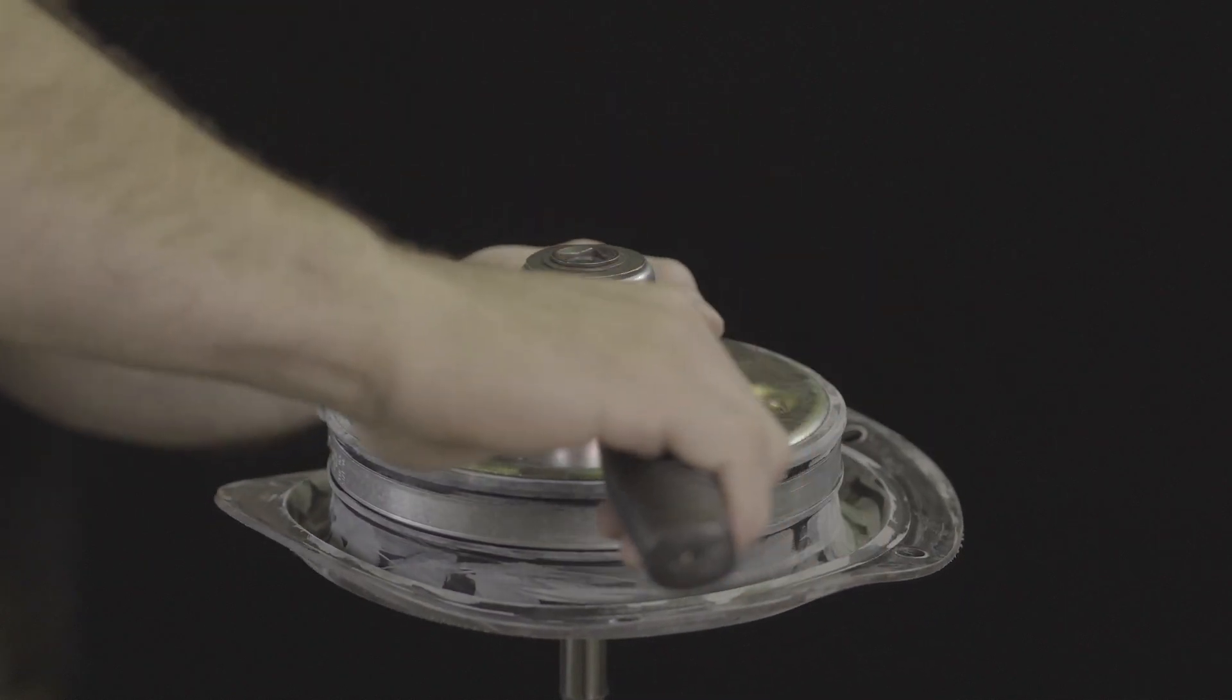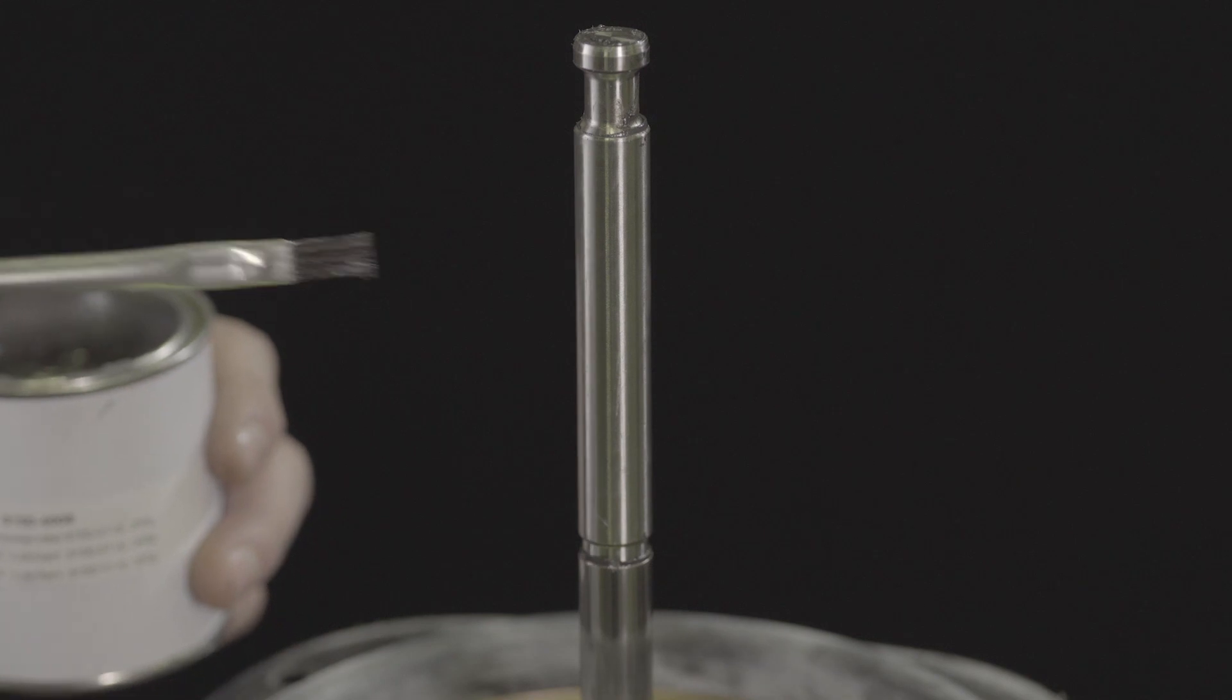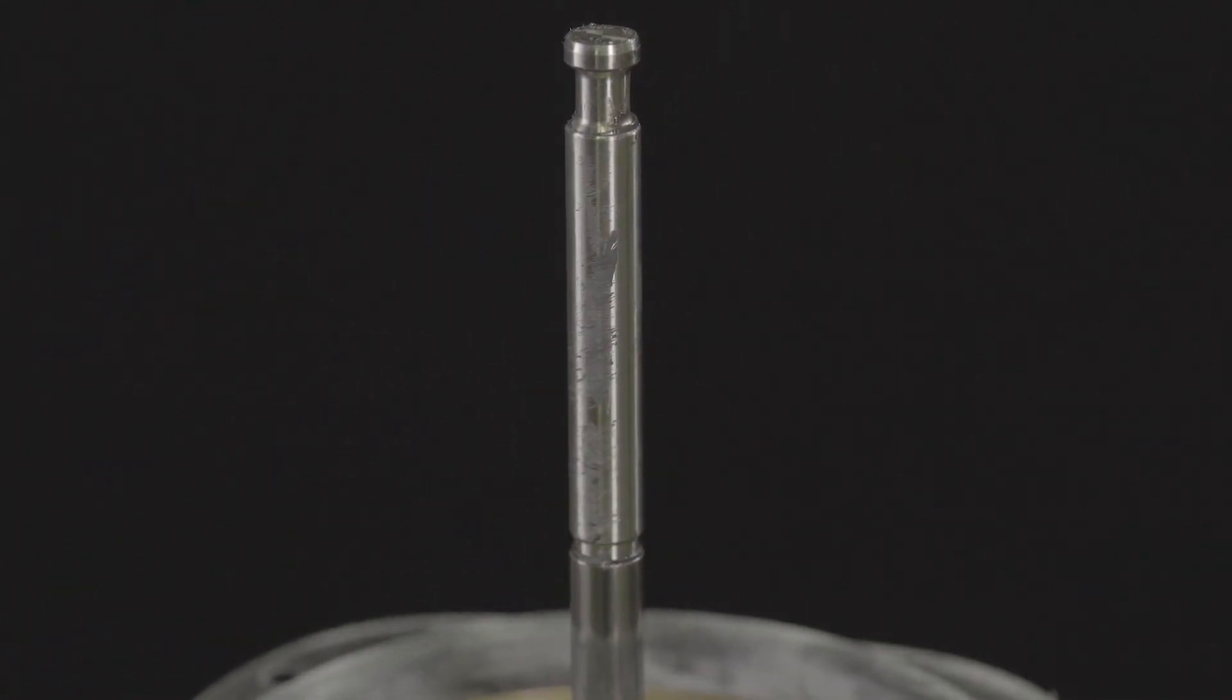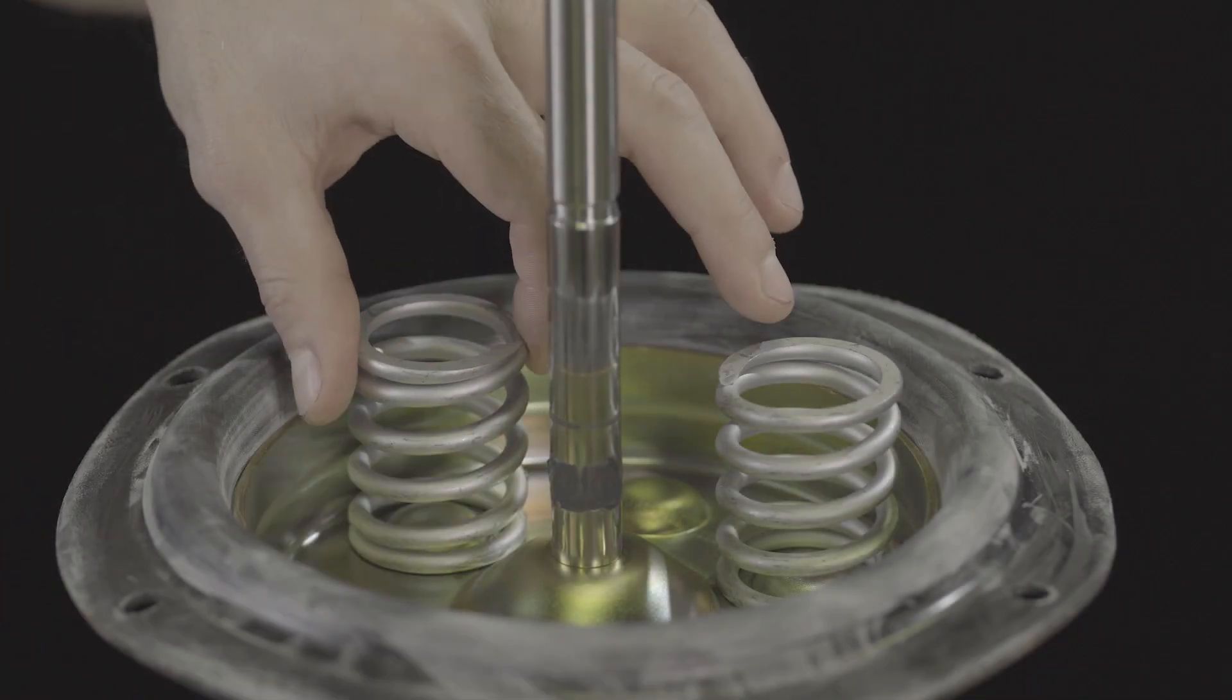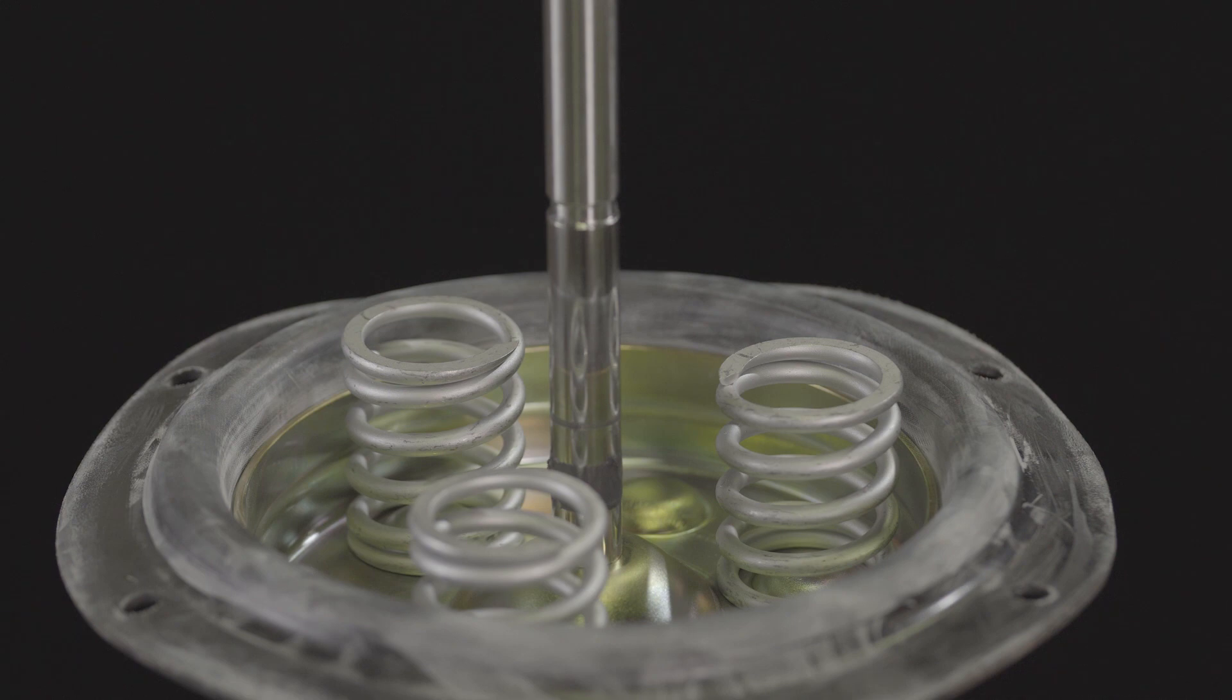Reinstall the collar nut. If necessary, apply a suitable lubricant to the actuator stem. Place the appropriate springs in the diaphragm plate, centering them in the intended recesses.